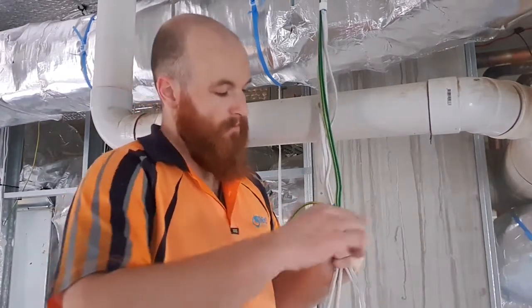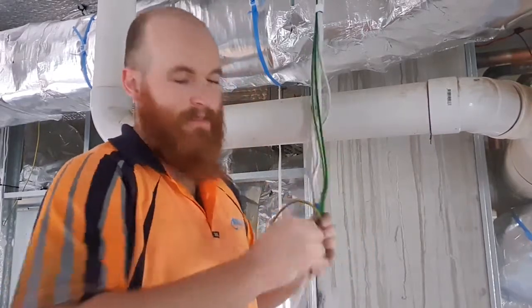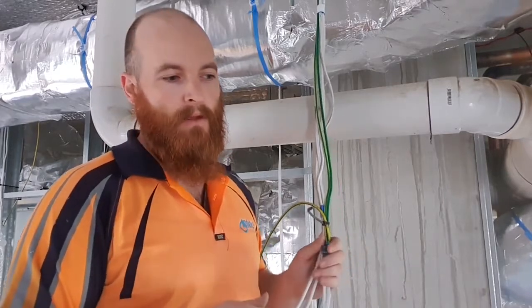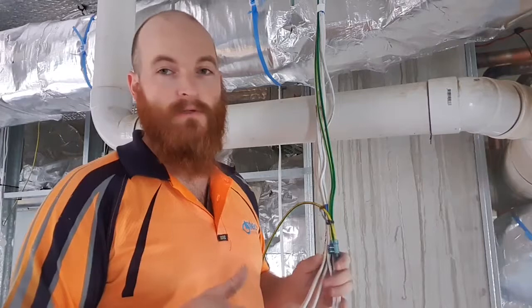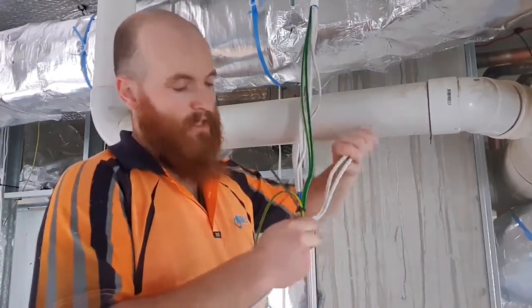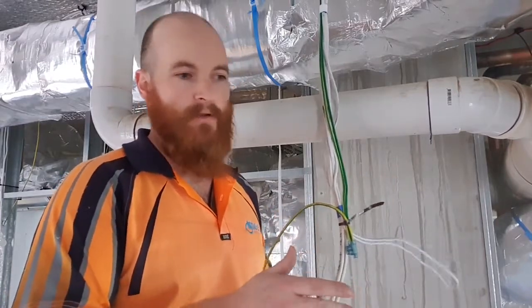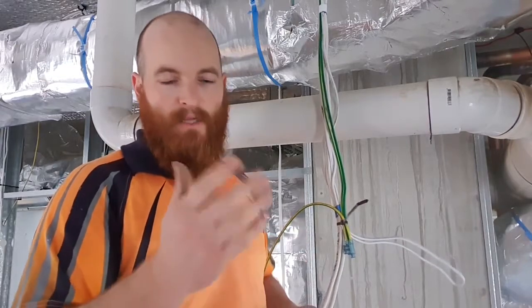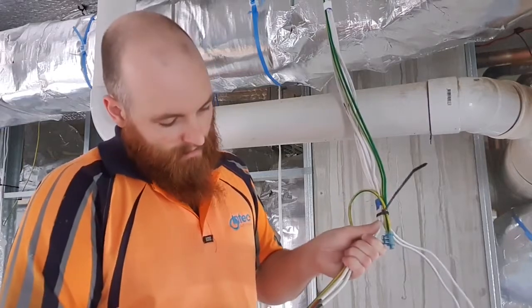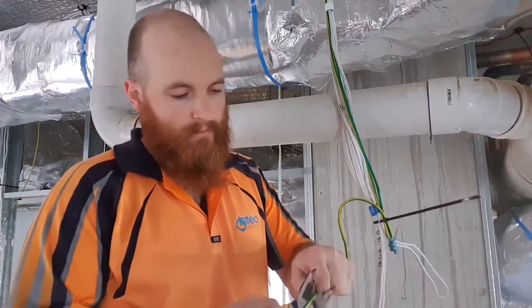And Dali, oh, I should explain. I want to appeal to more viewers than just us sparkies, but DALI stands for Digital Addressable Lighting Interface. It's a program that most light fittings use that have any sort of control with them. And you can have different control systems, but the lights will still be a DALI light. So you can have CBUS or KNX or a bunch of other ones, Dynalite. Heap of different manufacturers here in Australia, whether they're made in Australia or not.